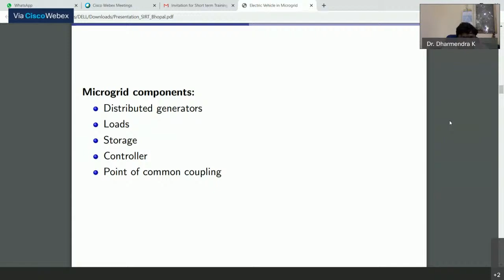I will discuss a bit more in the next slides about the controllers and the point of common coupling. What is point of common coupling? It is the point from where the microgrid is connected to the utility grid. The utility grid sees the microgrid as a single entity, simply connected at the point of common coupling. So these are the major five components of the microgrid. Please go to the next slide.